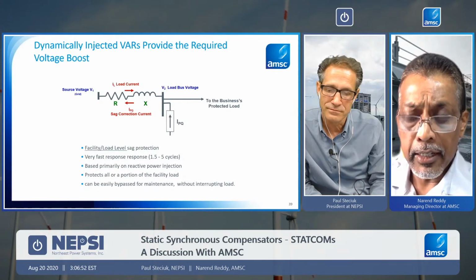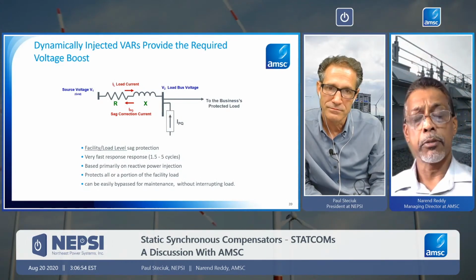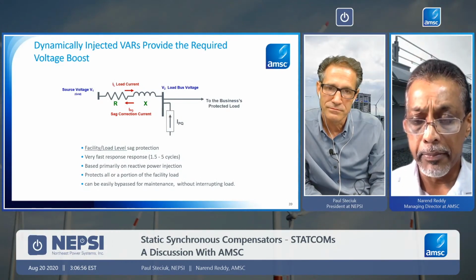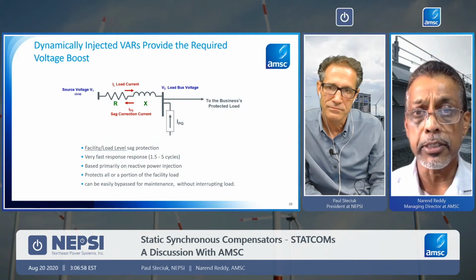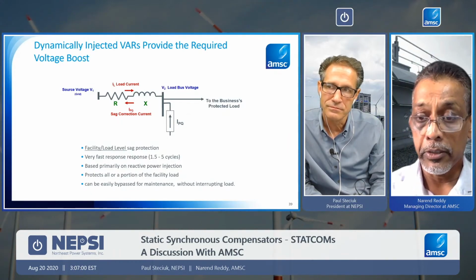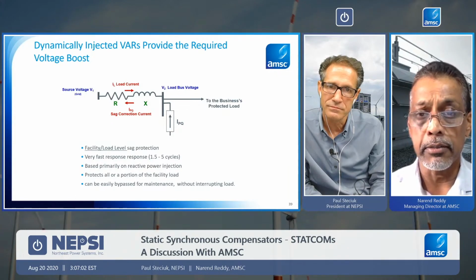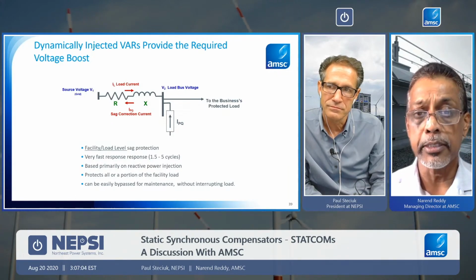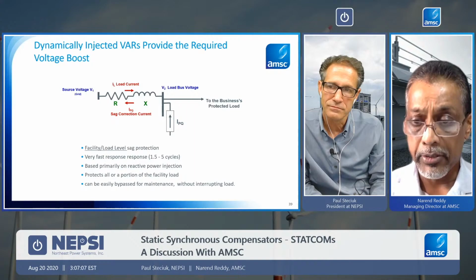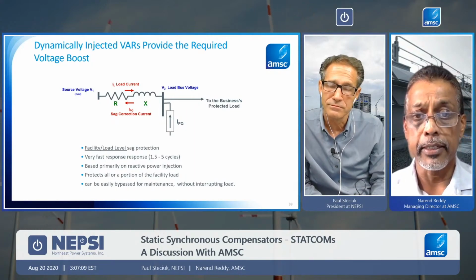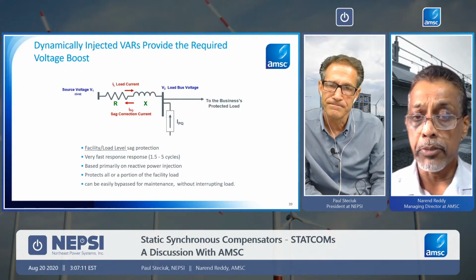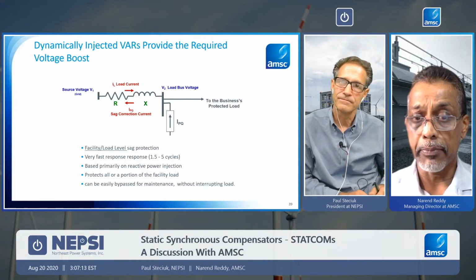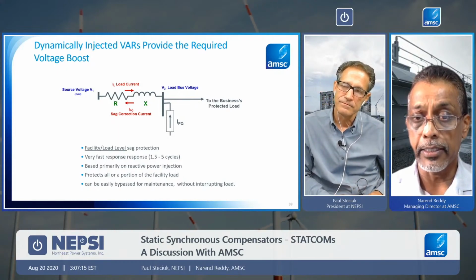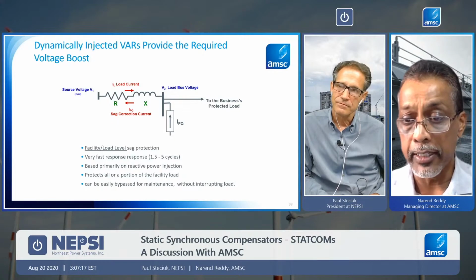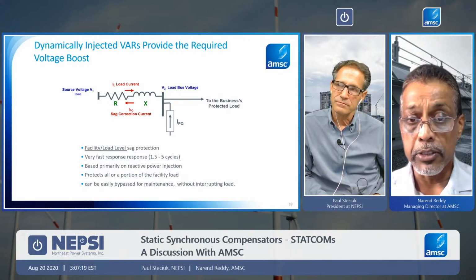So in this concept, what we have is what we call a PQIVR, Power Quality Industrial Voltage Restorer, which utilizes our STATCOM system, or the D-VAR STATCOM units, as well as NEPSI's cap banks. And it's really to provide what we call facility-level sag protection. It's very fast, a cycle and a half to 5 cycle response time.